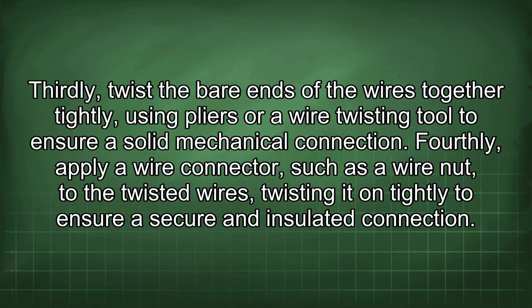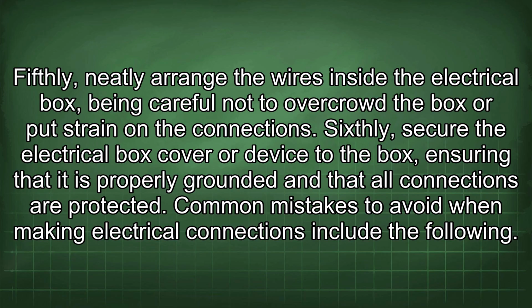Thirdly, twist the bare ends of the wires together tightly, using pliers or a wire twisting tool to ensure a solid mechanical connection. Fourthly, apply a wire connector, such as a wire nut, to the twisted wires, twisting it on tightly to ensure a secure and insulated connection. Fifthly, neatly arrange the wires inside the electrical box, being careful not to overcrowd the box or put strain on the connections. Sixthly, secure the electrical box cover or device to the box, ensuring that it is properly grounded and that all connections are protected.